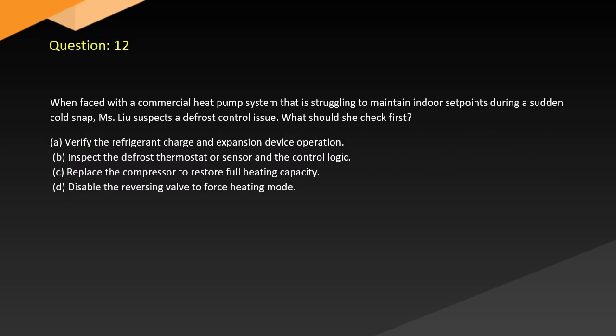Question 12. When faced with a commercial heat pump system that is struggling to maintain indoor set points during a sudden cold snap, Liu suspects a defrost control issue. What should she check first?